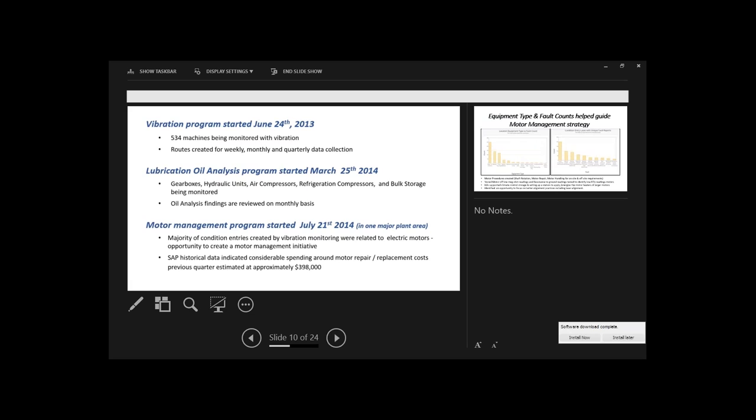What we're going to talk about today is kind of a case study from CB&I Plant Services. CB&I is Chicago Bridge and Iron. They run a service organization where they're in plants with technical people helping them with electrical reliability programs. CB&I does a lot more than that but the group we're talking to is the plant reliability. The client's petrochemical facility in Louisiana. CB&I has provided condition monitoring services for about two and a half years to this site. What they provide is vibration analysis, oil analysis, ultrasonics, motor management, infrared thermography, and visual inspection.